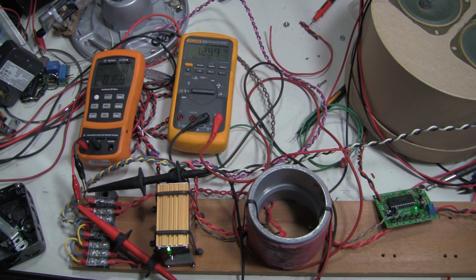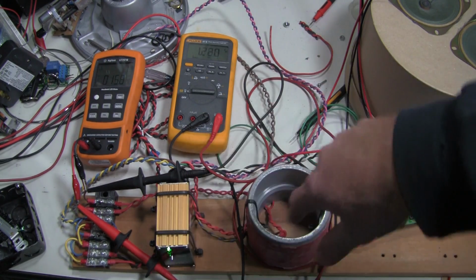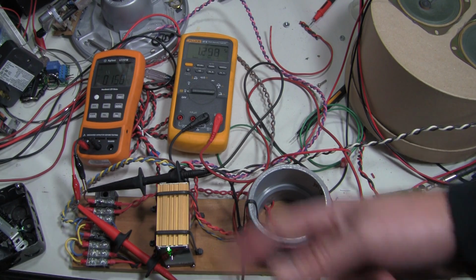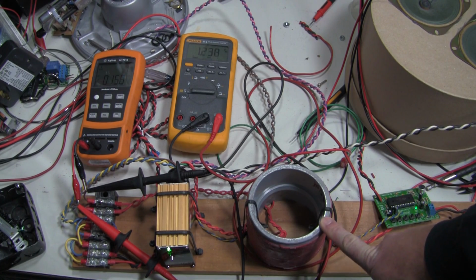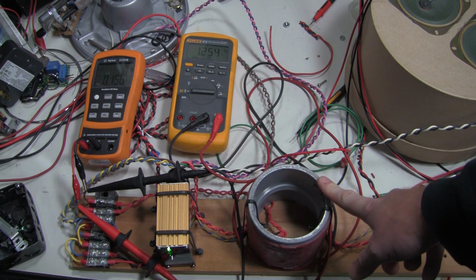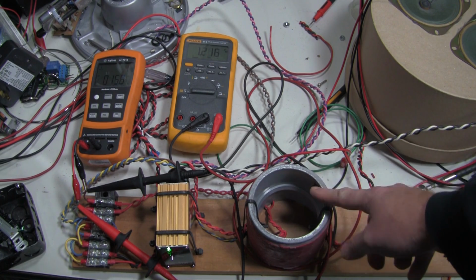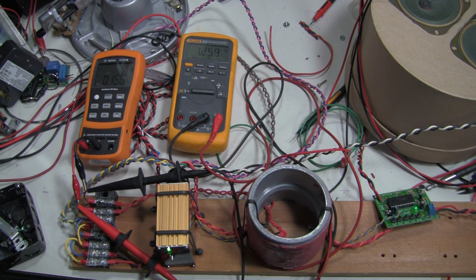how an inductive loop works, and some of the principles that we would use in order to test it, such as resistance, inductance, and then one of the other things that we test out in the field is leakage. It's an insulation test where we send 500 to 1,000 volts through the wire and see if there's any leakage to ground. If not, then we pour water over it to help increase the conduction, and then run the test again at 500 and sometimes 1,000 volts to see if there's any change in the insulation resistance after we put water on it, and help the conductivity of any cracks in the insulation.